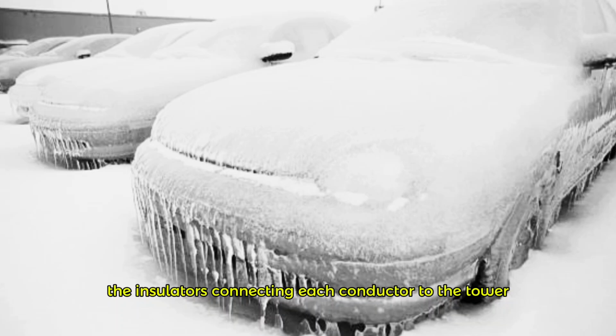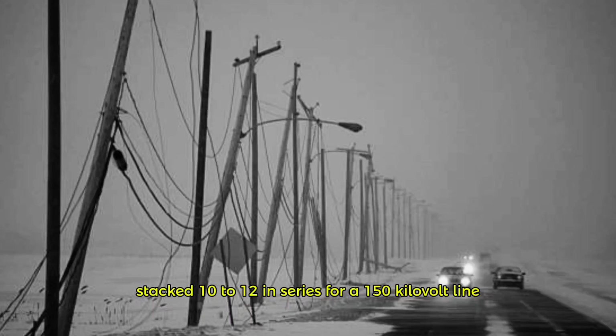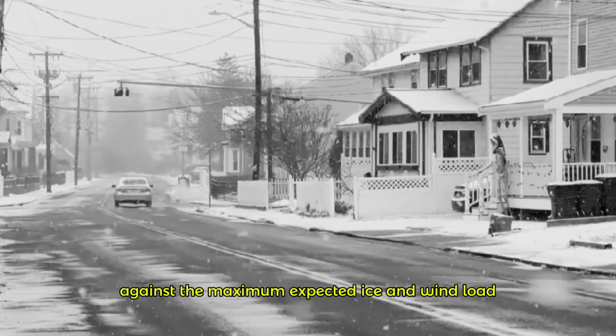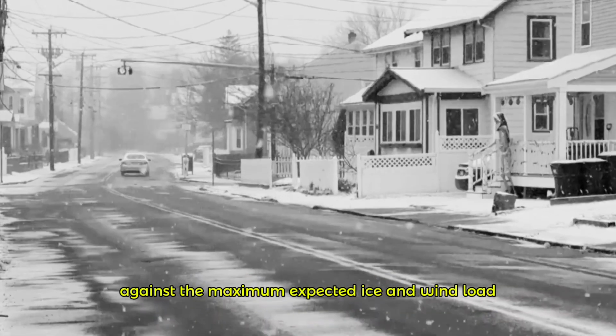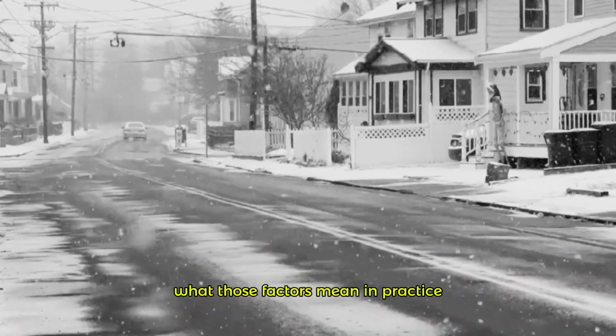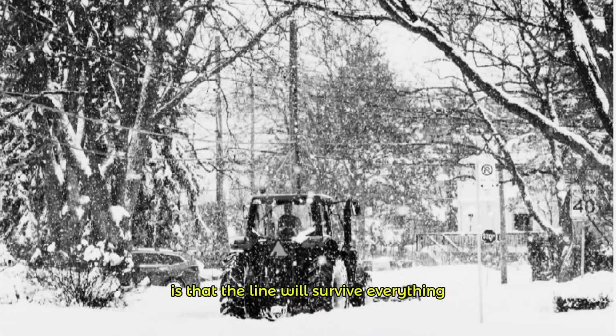The insulators connecting each conductor to the tower are porcelain or tempered glass discs, each rated for 15 kilovolts, stacked 10 to 12 in series for a 150 kilovolt line. They are designed to a safety factor of 3 against electrical failure. The tower attachment hardware is designed to a factor of 5 against the maximum expected ice and wind load. What those factors mean in practice is that the line will survive everything short of an extreme event.